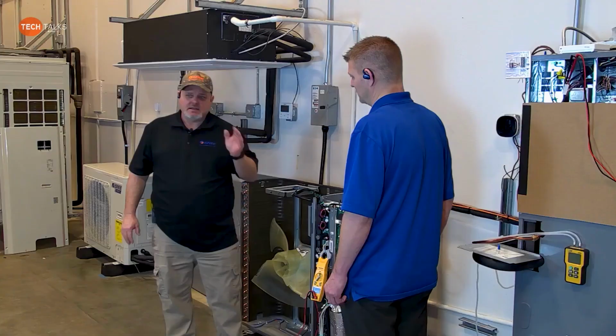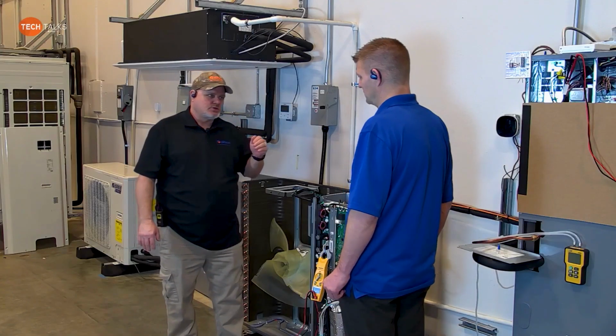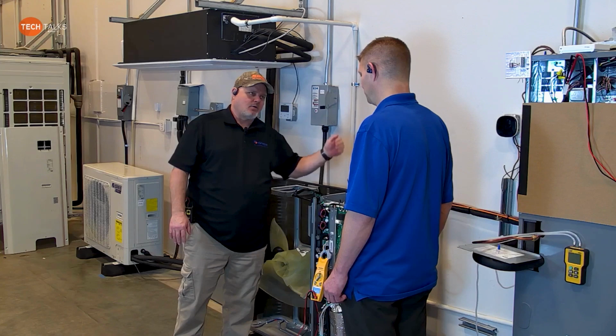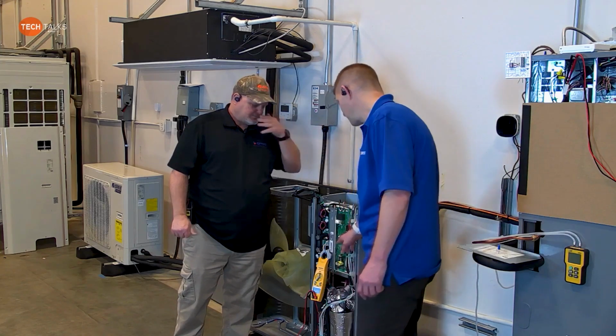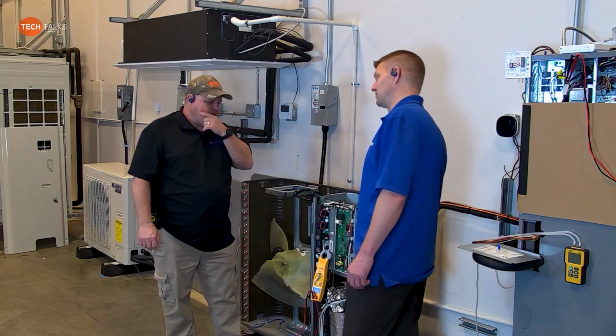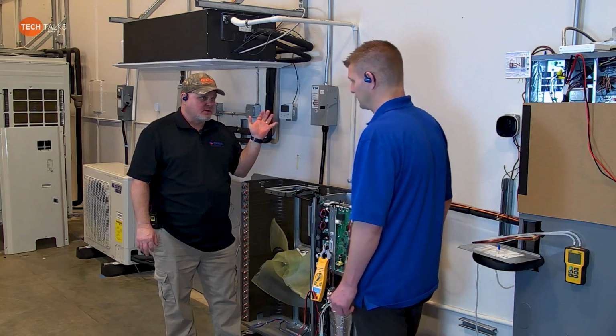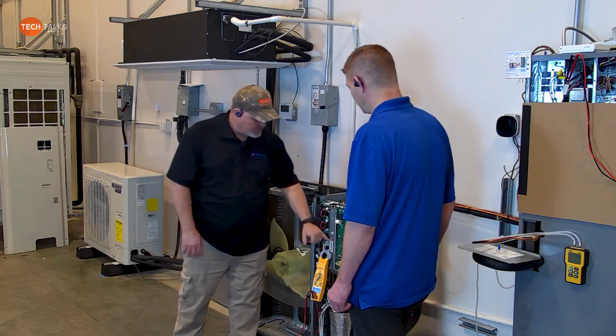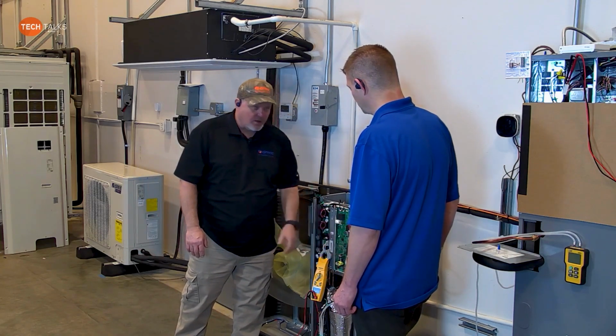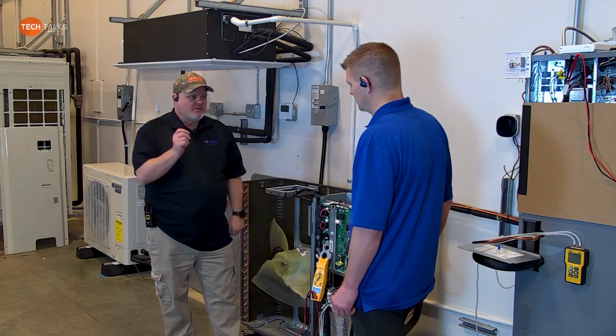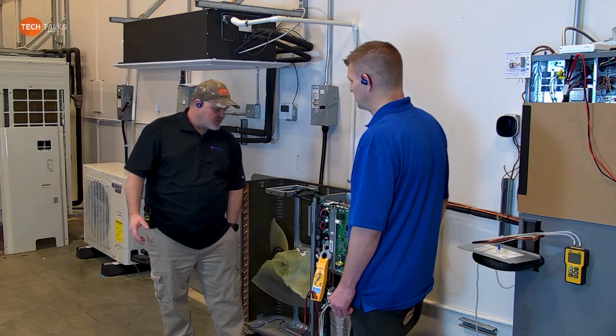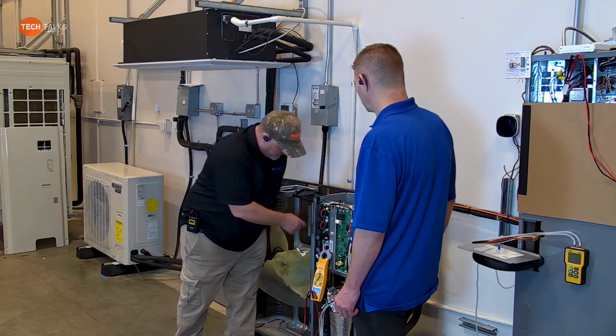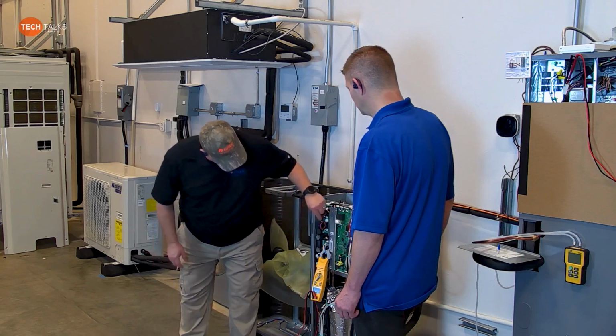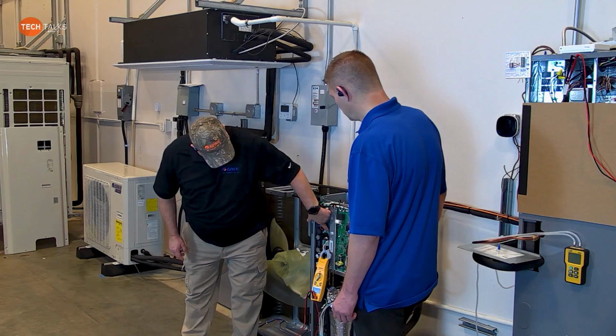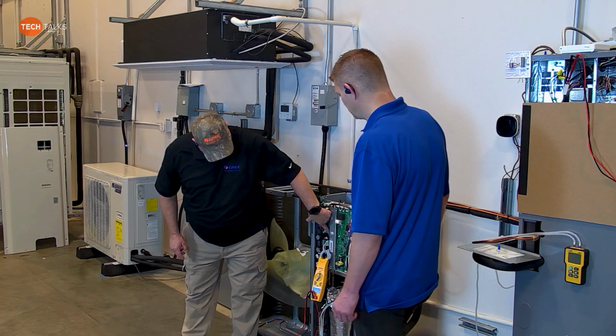Keep in mind, anytime you're adjusting dip switches, you have to do it with the power off. You have to turn power off and wait for this display to shut off too. Yeah, I'd like the DC bus to dissipate. And once we power it up, you'll see there's a red light in here, and we'll point it out later on. It's pretty vivid. Yep. And if you're not checking the DC bus, which you can check from right here, if Nick can get a close-up on that where my finger's pointing.